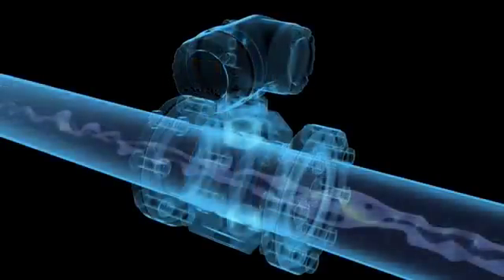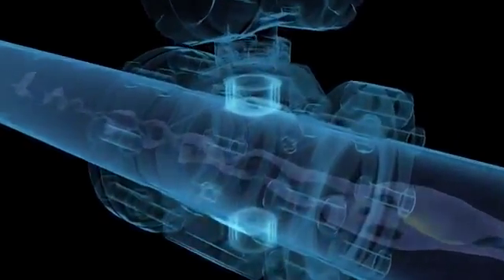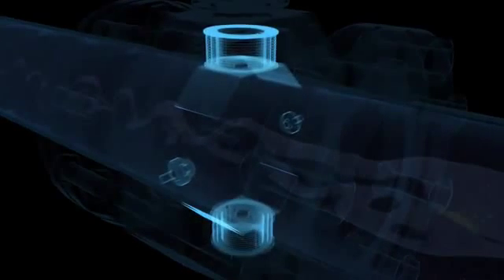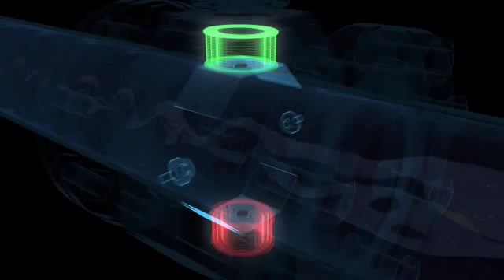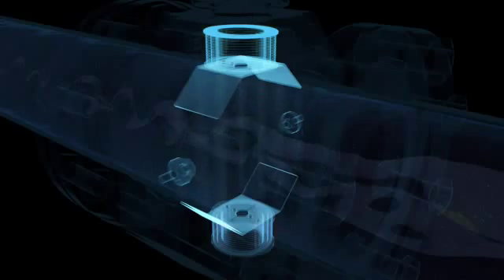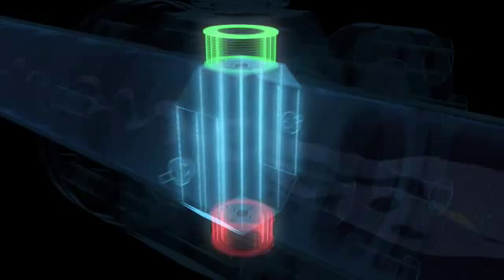Let's take a closer look at how this measurement method works. Two field coils are located inside each electromagnetic flow meter. With the help of what are termed pole shoes, these coils generate a constant magnetic field over the entire cross-section of the measuring tube.